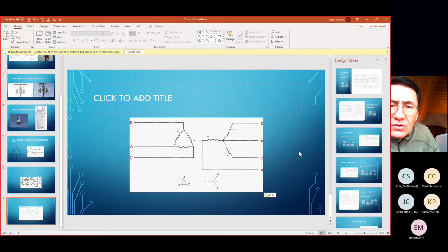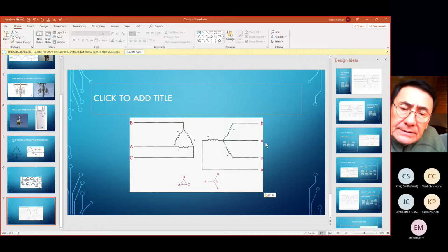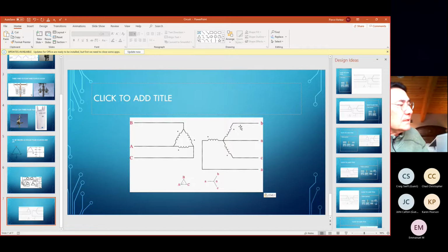You must ensure that you have a ground on your three-phase supply. If you do not, that little RC circuit to ground becomes your ground. So if you're getting a delta Y, but the center tap is not grounded, therefore you've got a 3-line power pole secondary, you will blow this EMC filter up pretty quickly. It's a caution that I suggest that you ensure that you have taken account of, because the failure will be quick and it'll be expensive.